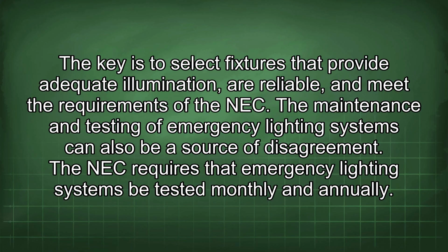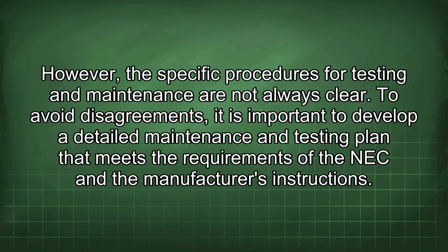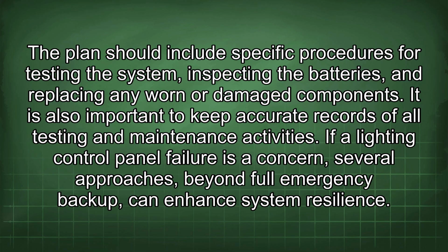The maintenance and testing of emergency lighting systems can also be a source of disagreement. The NEC requires that emergency lighting systems be tested monthly and annually. However, the specific procedures for testing and maintenance are not always clear. To avoid disagreements, it is important to develop a detailed maintenance and testing plan that meets the requirements of the NEC and the manufacturer's instructions. The plan should include specific procedures for testing the system, inspecting the batteries, and replacing any worn or damaged components. It is also important to keep accurate records of all testing and maintenance activities.